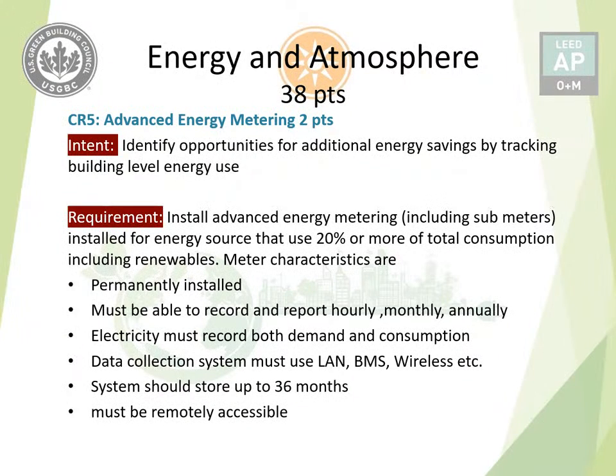The prerequisite will also apply, but these meters are more smart, able to record and report hourly, monthly, or annually, meaning they would usually be connected to your building management system. Electricity must record both demand and consumption, because utility companies charge you per demand - your KVA - and your consumption. This might identify an opportunity to save if you're using less but your demand is more, so in the next months you can reduce your demand as well.